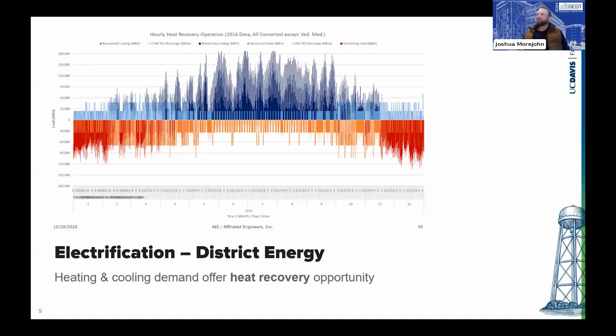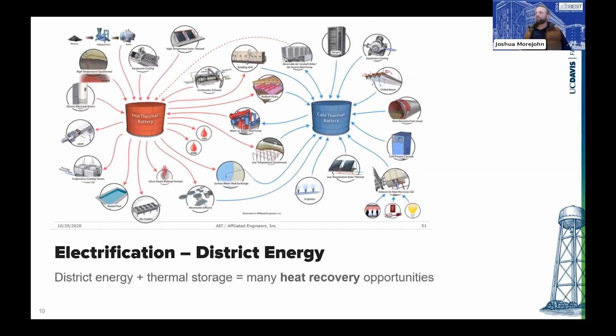One important thing is this is also including a hot water thermal energy storage tank, so we can do daily storage, essentially collecting heat through the day when we're cooling, and then providing the heat to the campus in the night and the morning when we're heating, which we do due to our climate. We're doing that throughout the year, have some heating and cooling load because of our diurnal swing in temperatures. So that's really what we're going after with this district energy conversion, and the big opportunity for us is to leverage heat recovery and also provide a pathway to full electrification.